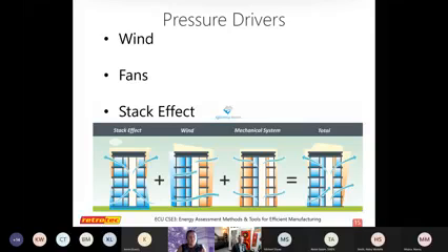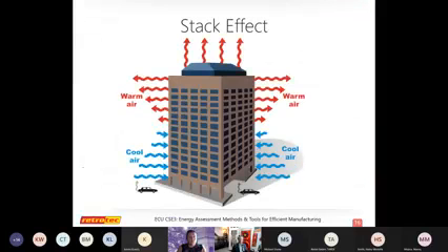But stack effect is another one that plays a really big role here, especially in manufacturing buildings. In the winter, what happens is that hot air rises and escapes out the top, and at the same rate, it pulls in cold air from the bottom. So if we have maybe 10 pascals of pressure, or negative 10 here at the top, we could have positive 10 coming in. So it's going to be equal on both ends usually. That's one way that we can help differentiate that. If we have a lower pressure at the top and a higher pressure at the bottom, then that means that more of our leakage is at the top than the bottom.